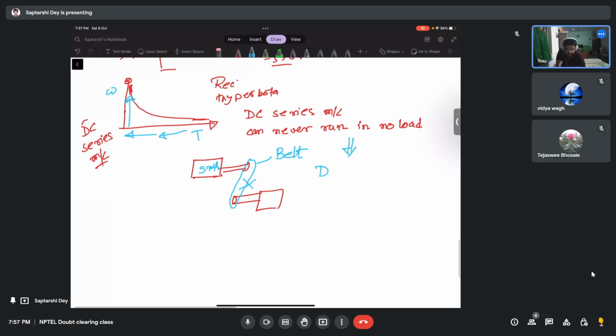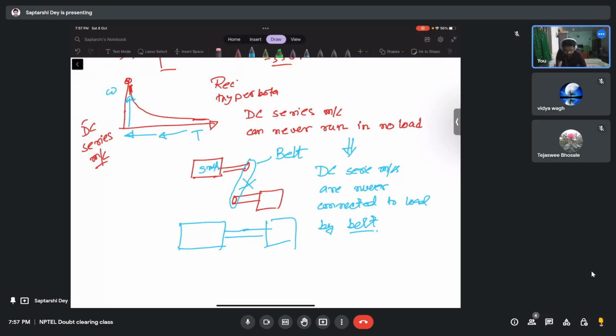This is why DC series machines are never connected to the load by belt. They are always directly coupled. This is the motor, this is the load. They are directly coupled like this. They are never connected through a belt. If this is the connection, then the chance is very small, compared to a belt snapping, that this machine will suddenly start running at no load. That is why DC series machines are never connected to the load through a belt. This is a very important question, asked many times in many places.